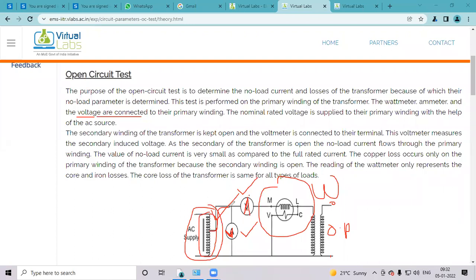So this is the auto transformer or the VARIAC. We are applying variable supply, meaning whatever supply we require, we use the auto transformer to vary it. So that means while conducting the open circuit test, this test can be conducted on full supply voltage. When full supply voltage is applied to the primary side, according to the transformer principle there is mutual induction between the two coils, so there will be mutual induction principle between these two coils, and some induced EMF will be present in the secondary side.